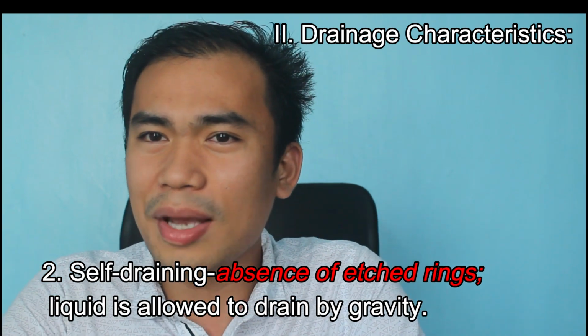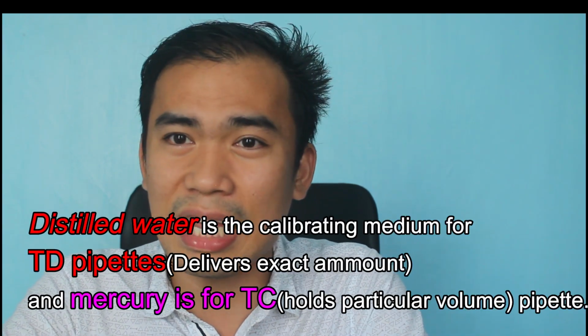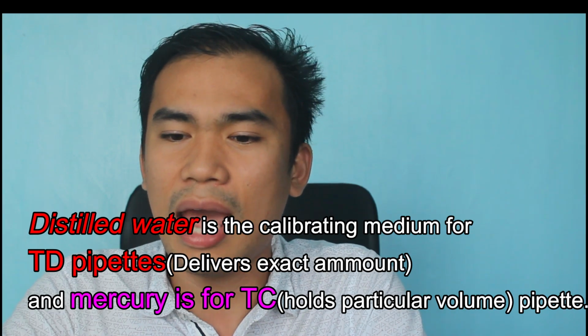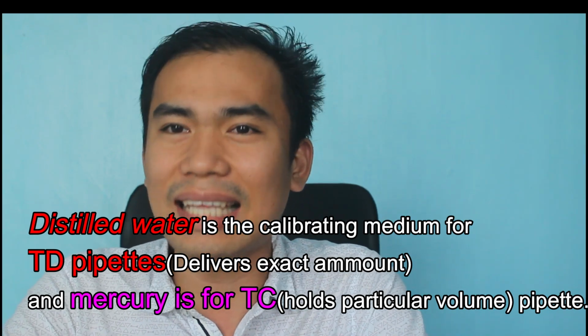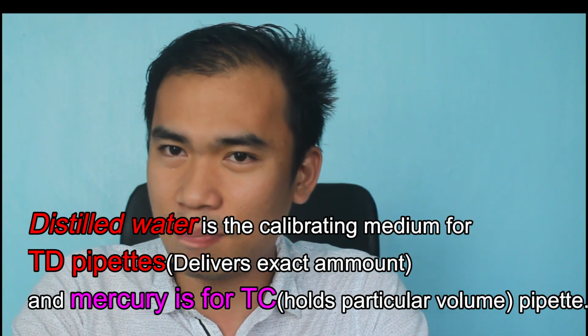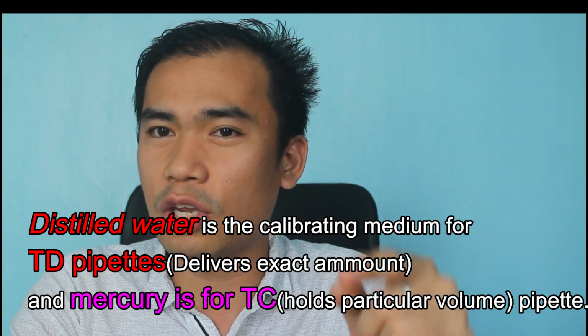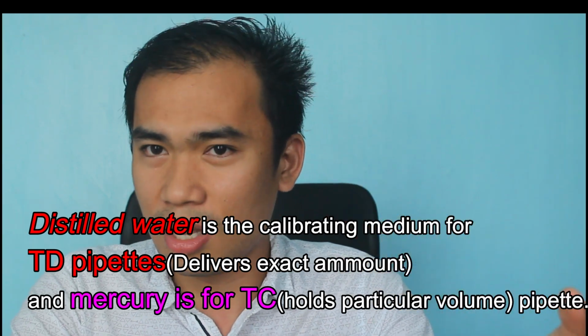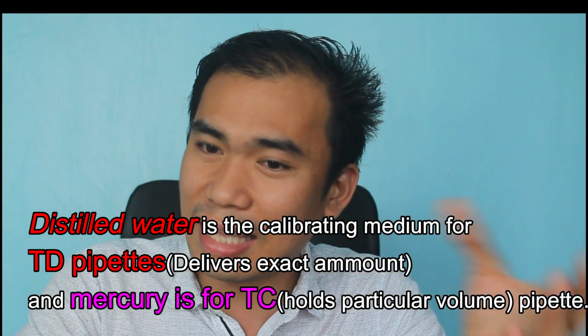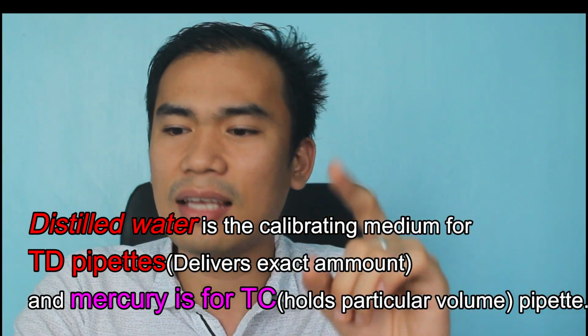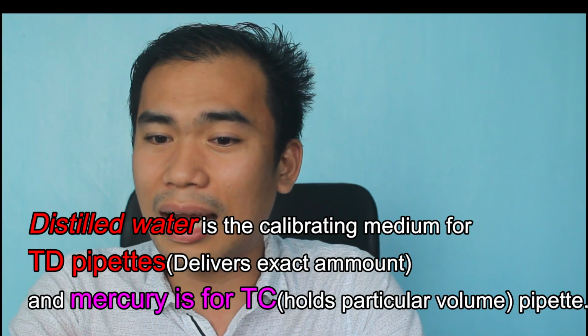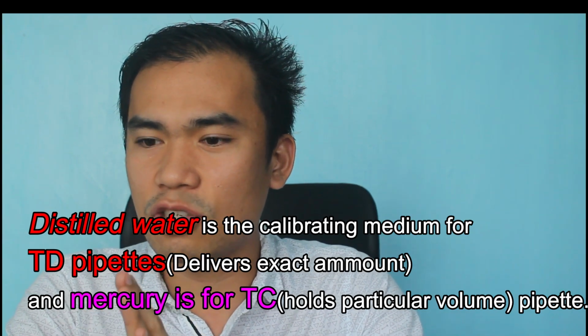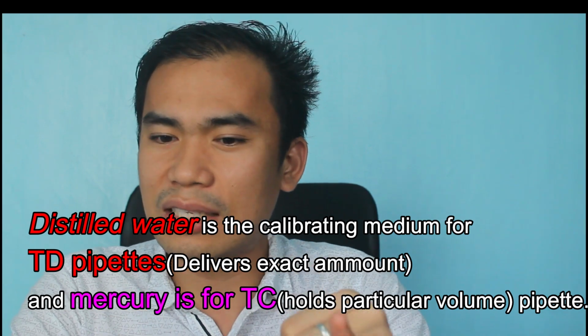Okay? So always remember, what is the calibration medium for the TD pipettes? The answer is the calibrating medium for TD pipette is the distilled water. And mercury naman is for TC, holds particular volume pipette, okay? So distilled water is for your TD, while mercury is for TC. TD delivers the exact amount, TC holds particular volume. Don't forget the calibration, okay? For calibrating medium, distilled water for your TD, mercury for your TC.